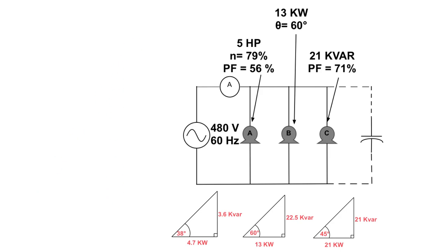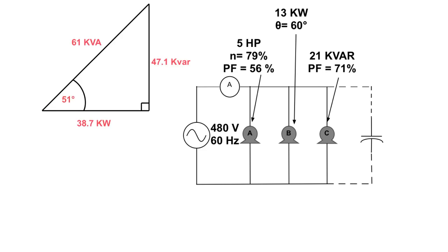Then, I'm going to work out my overall kVA. Boom! There you go. I went 4.7 plus 13 plus 21 gives me 38.7 kilowatts. I went 3.6 plus 22.5 plus 21 gave me 47.1 kVAR. Using the power of Pythagoras, this squared plus this squared gives the square root of that. That's 61 kVA. With that now, I worked out that my angle is 51 degrees. Just using you can use sine, cosine, tangent, whatever you want.